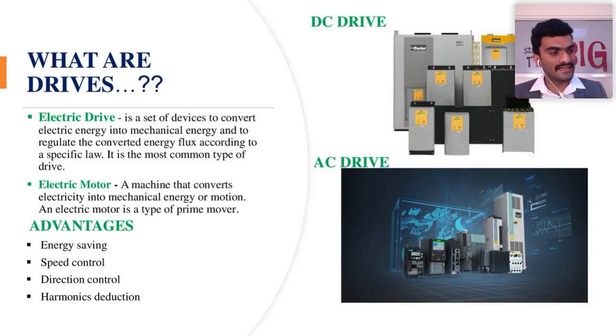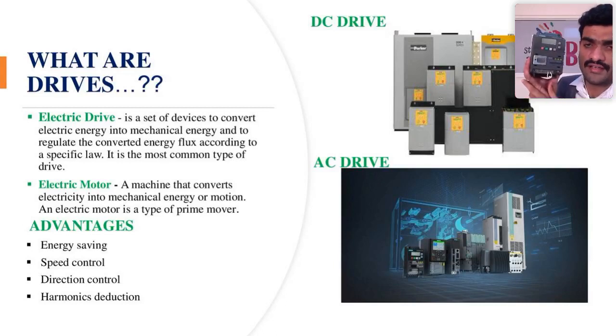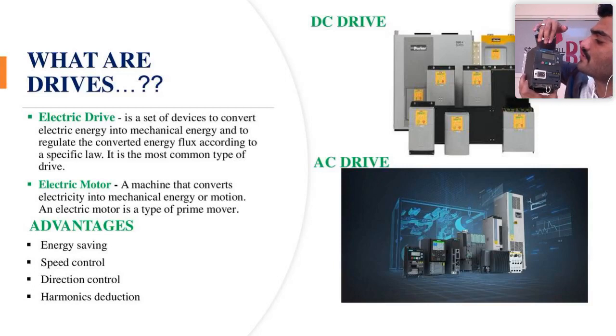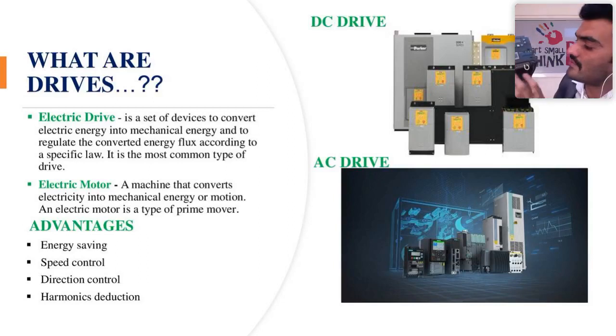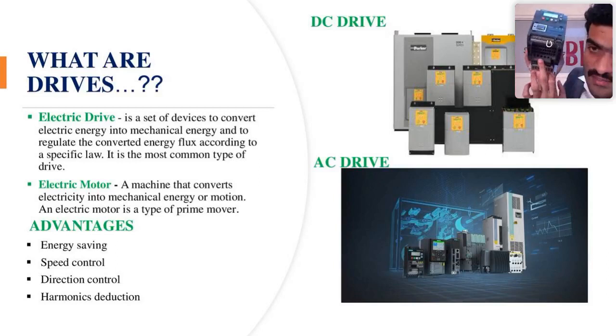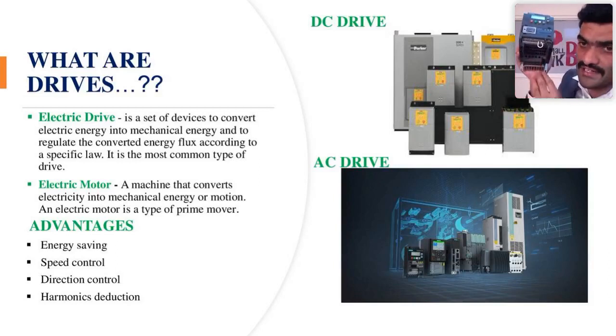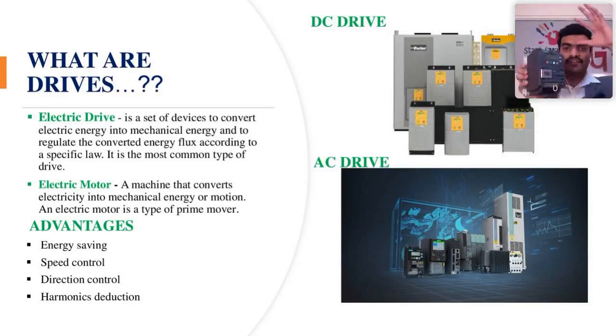So in the case of a drive, this is the VFD. How will it be connected? First of all, we connect your three-phase supply, your line supply, here. Whether it is three-phase or single-phase, in single-phase we connect phase and neutral, and in three-phase we connect three phases. This drive will have output terminals UVW. This UVW is again three-wire, and it will be connected to your motor. So between your main supply and motor, this drive will be there.